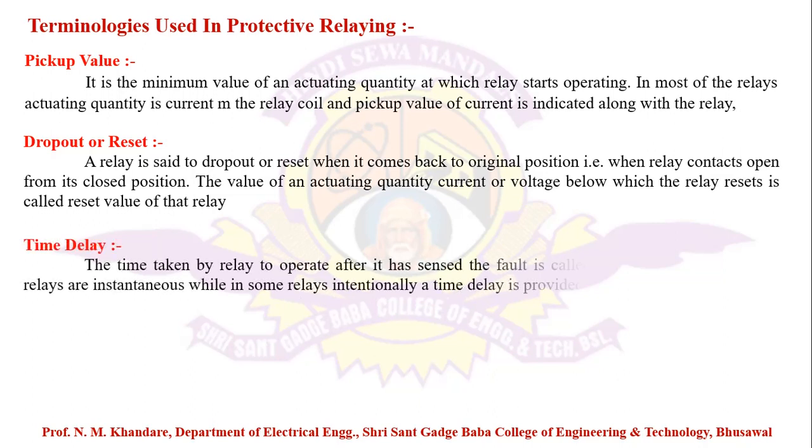Next is the time delay. In some cases we need time to elapse before the operation of relays, because the switching currents are so high and the system does not identify whether it is a switching current or a fault current. If the switching current is high, for example when connecting capacitors, and no time delay is given, then due to the normal condition the relay can pick up.